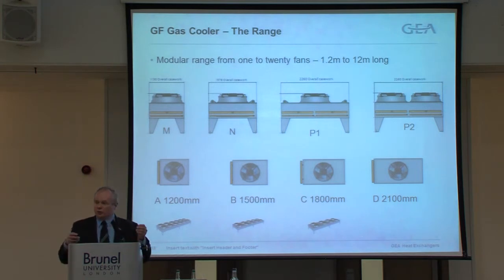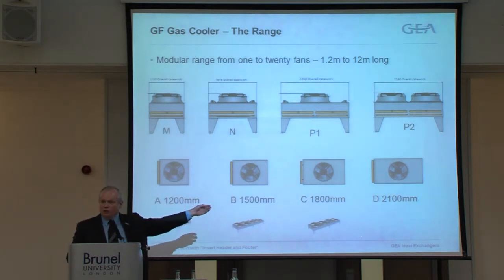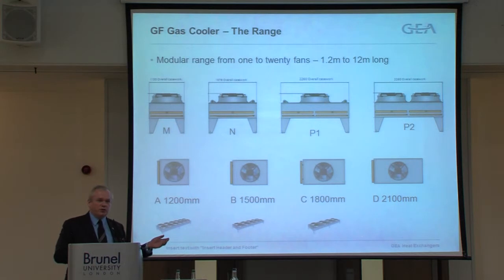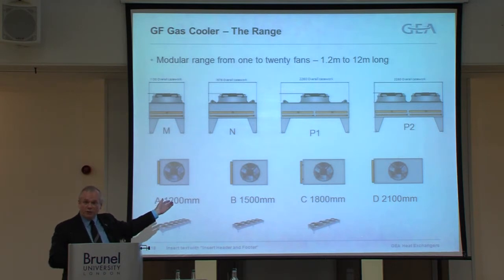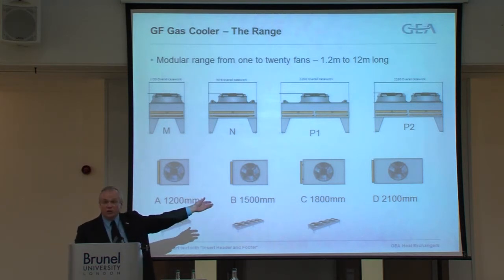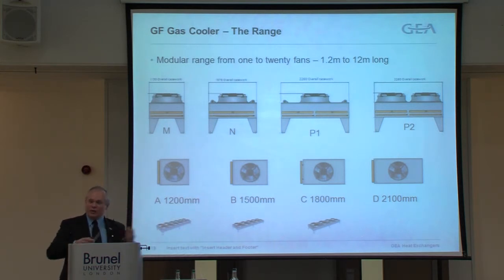So if you're looking for tremendous energy efficiency, you're going for the D module unit, you have a large amount of fixed surface, minimum number of fans. If you've got a heat exchange matrix that's made of copper, and it's costing you a lot of money, you may want to actually come down to an A module and then have more fans on it. If you need something that's very quiet, you want to reduce the number of fans that you're utilising, you go to a B or a C module. So there's a tremendous amount of options that an engineer's actually got now, best described on a computer selection software.